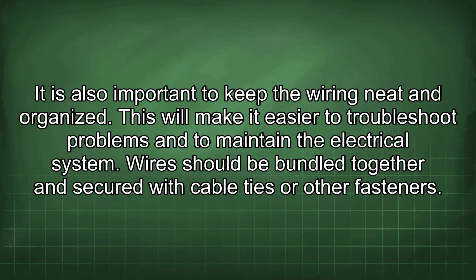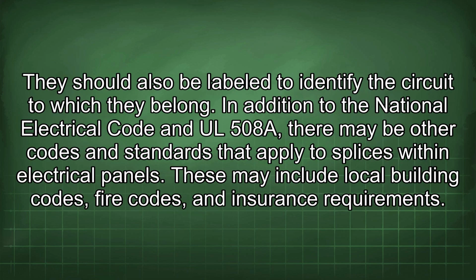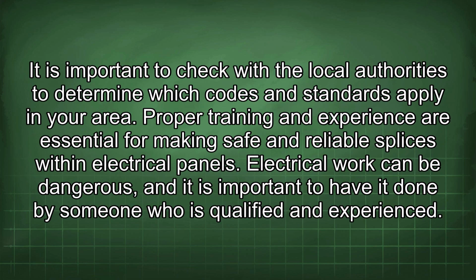It is also important to keep the wiring neat and organized. This will make it easier to troubleshoot problems and to maintain the electrical system. Wires should be bundled together and secured with cable ties or other fasteners. They should also be labeled to identify the circuit to which they belong. In addition to the National Electrical Code and UL 508A, there may be other codes and standards that apply to splices within electrical panels. These may include local building codes, fire codes, and insurance requirements. It is important to check with the local authorities to determine which codes and standards apply in your area.